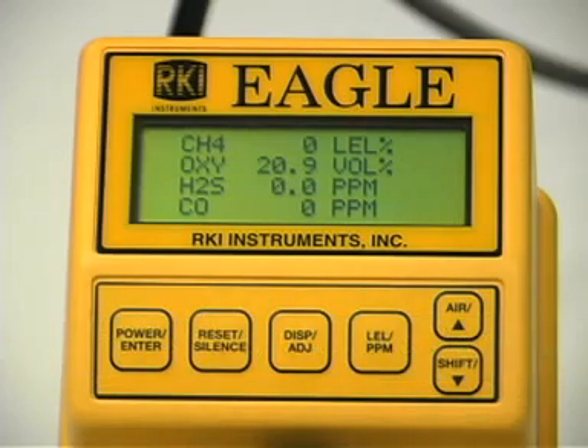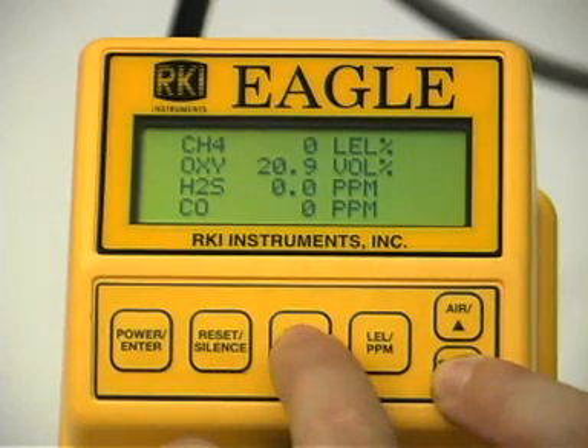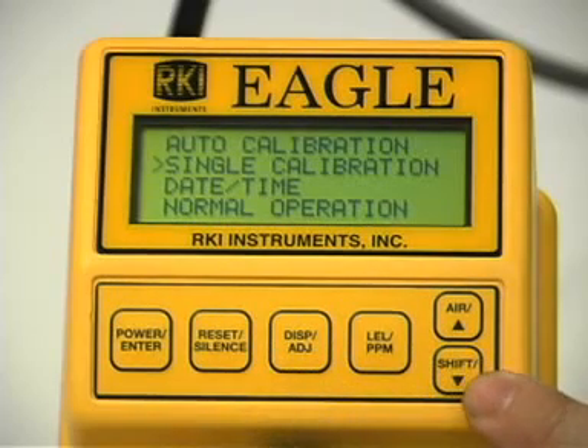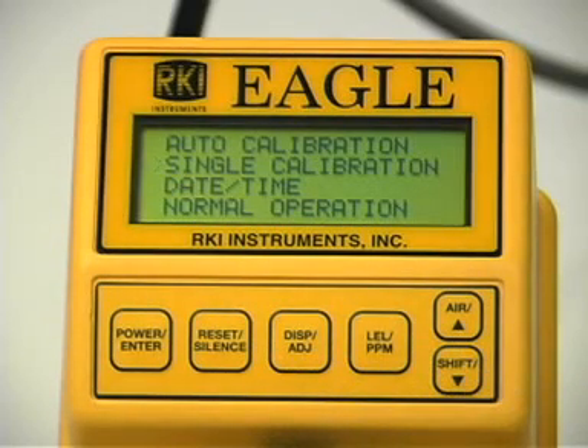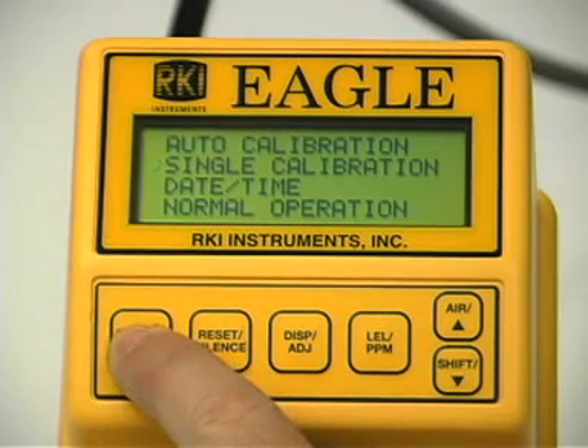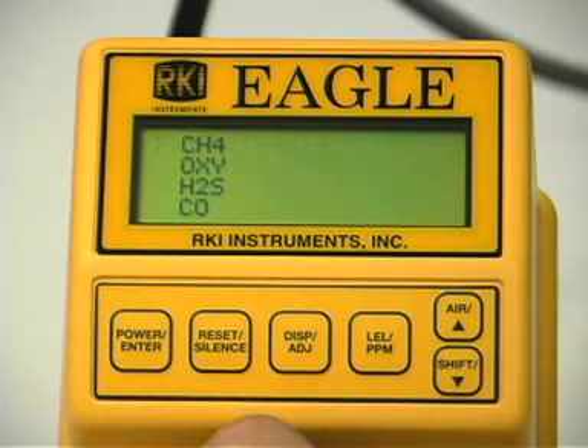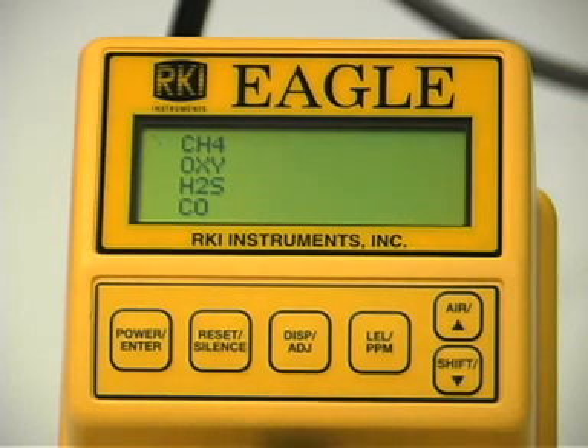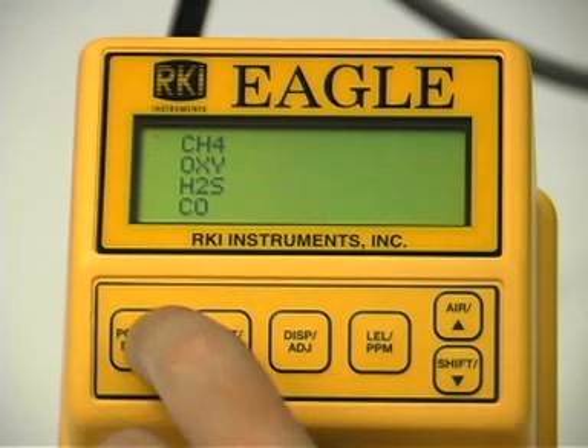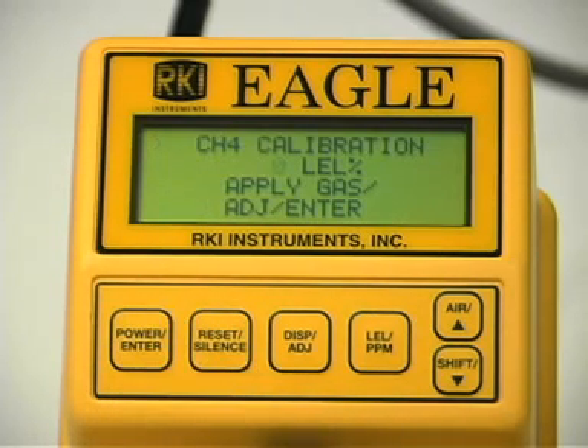Press and hold the shift down button, then simultaneously press the display adjust button to display the calibration menu. Use the up and down button to place the prompt next to the single calibration menu option. Press the enter button to open the single calibration menu. Use the up or down button to place the prompt next to the channel to be calibrated. Press the enter button. The single calibration screen displays for the channel you selected and the gas reading flashes.